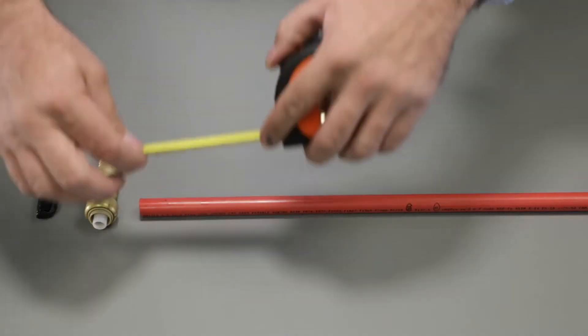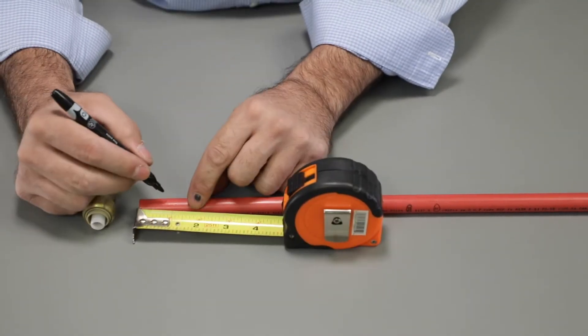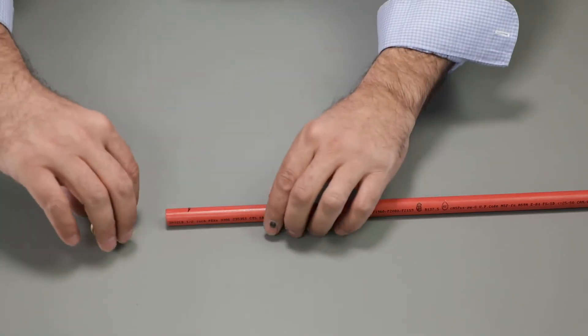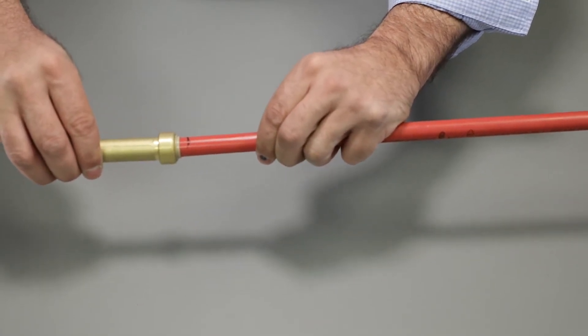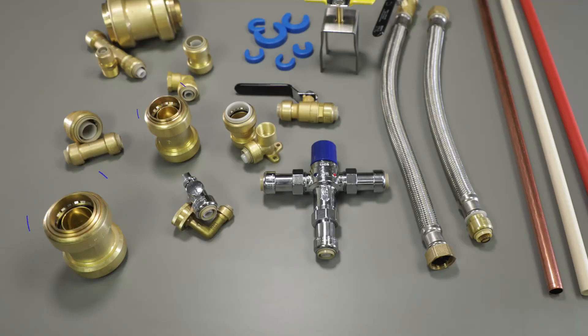To install, be sure the pipe is cut cleanly and squarely. Next, measure and mark the depth needed for the fitting you're working with. Push the SharkBite fitting onto the pipe at the install depth mark. The stainless steel gripper ring bites the pipe, holding it firmly in place. A rugged EPDM O-ring seals the connection.